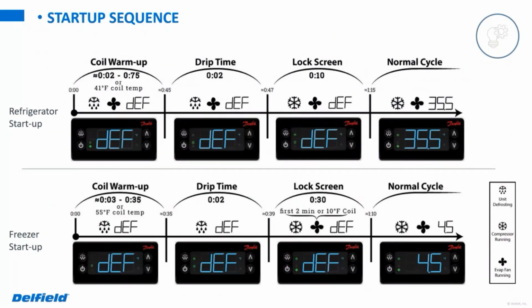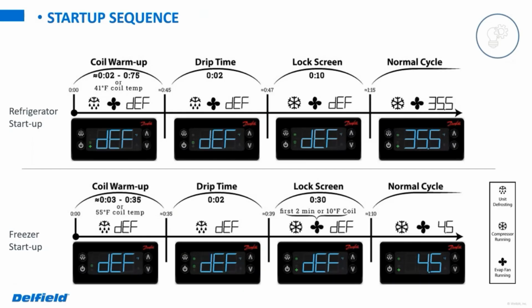One thing to note, troubleshooting wise: you're running one of these and your fan does not kick on for the first 2 minutes until the 2 minutes has elapsed, you most likely have something going on refrigeration wise, or a probe reading incorrectly. Either one of those could affect that. We'll show you how to read the probes here shortly, but that is something to keep in the back of your mind. All right, so moving on from there.